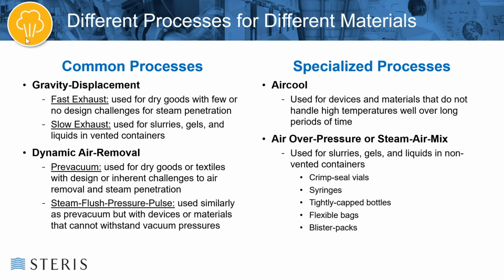And then for the dynamic air removal process, again there are two different kinds. You have what's called a pre-vacuum, and then you have a steam flush pressure pulse, or SFPP. The pre-vacuum is used for dry goods or textiles with design challenges that make it difficult to pull air out of the devices or the packaging or whatever is inside the chamber. The steam flush pressure pulse is also a dynamic air removal system, but this is primarily used for devices or packaging that can't withstand vacuum pressures.